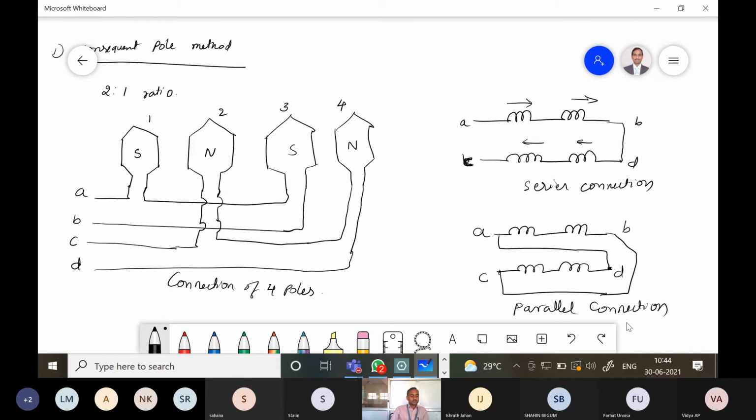In the pole changing motor, the rotor must be a squirrel cage to avoid the complications caused by reconnection of the rotor winding. So this method is especially used in squirrel cage induction motors. It is not used for slip ring motors because there is some complication in the construction of poles.